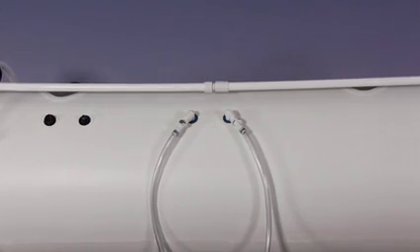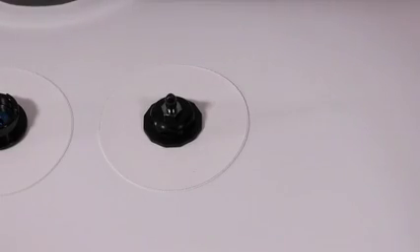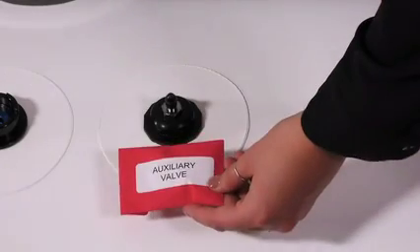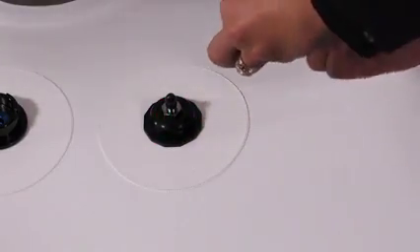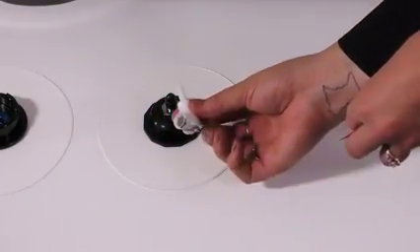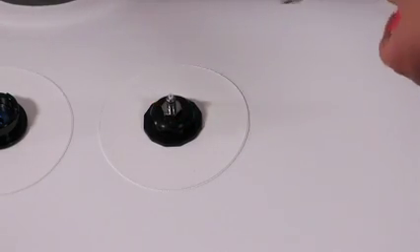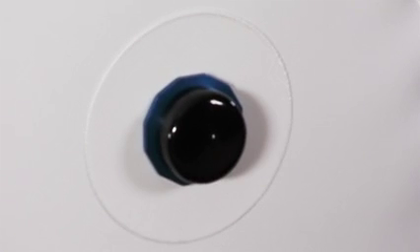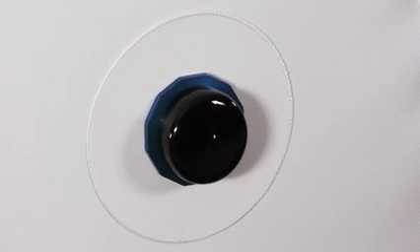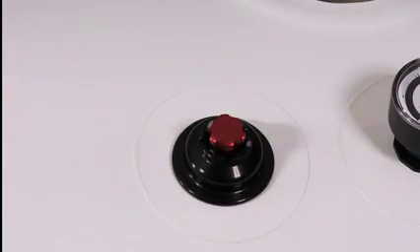On the back of the chamber there are 2 fill valves. Next to the window is an auxiliary port where the auxiliary valve attaches. This small auxiliary valve is located in your packet along with the zipper cleaner, zipper lubricant, and thumb drive. There are also 2 additional ports, one at each end of the chamber. These are for additional accessories. The red deflation valve is designed to turn in either direction to release air from the chamber.